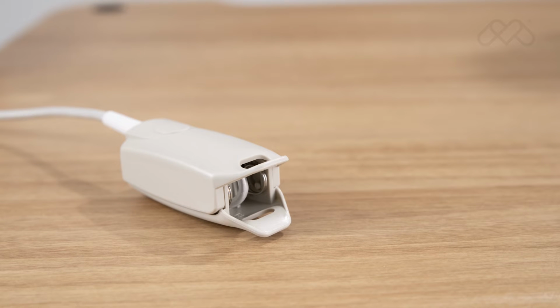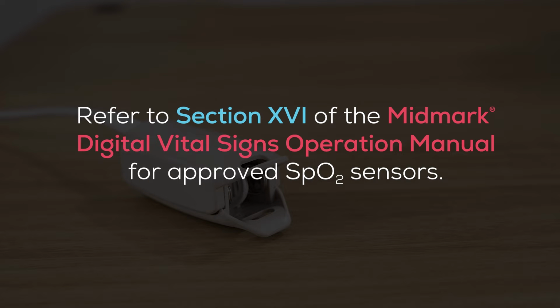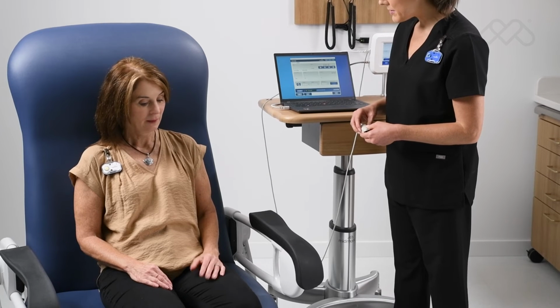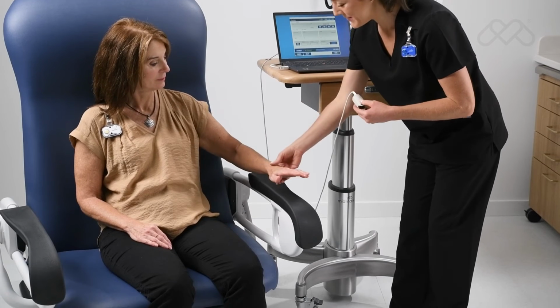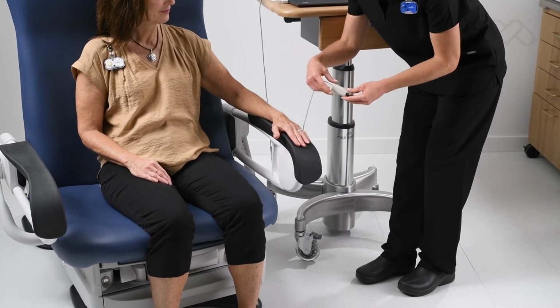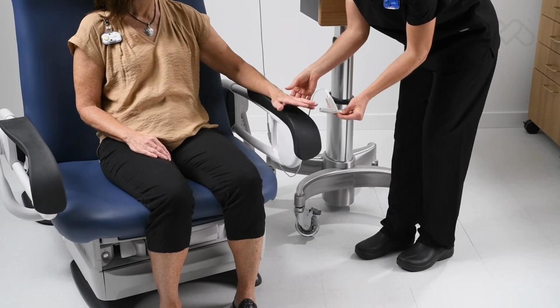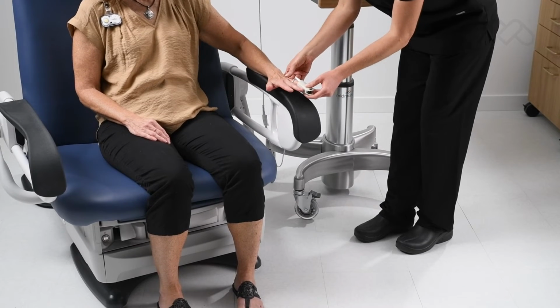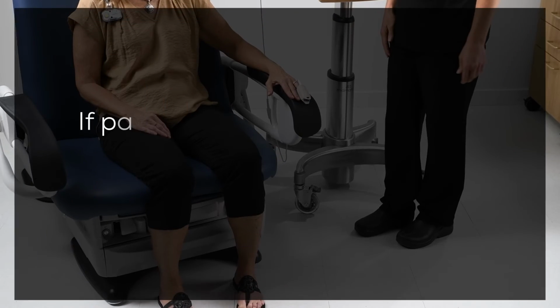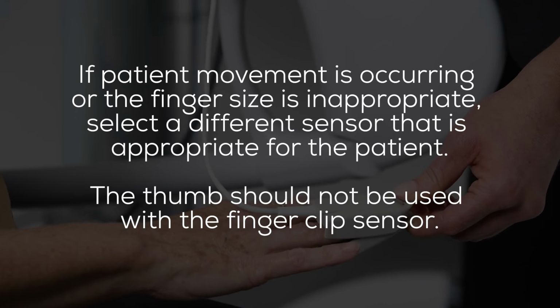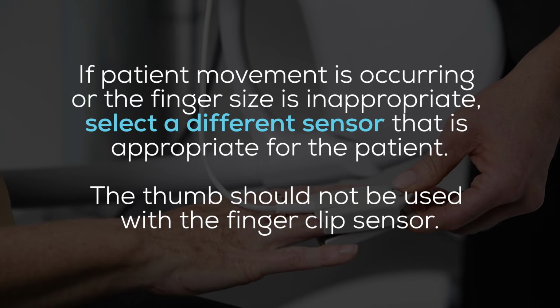clip sensor. Carefully read the sensor directions before using. To perform the SpO2 measurement, insert the patient's finger completely into the sensor. Place the sensor with the LED light position on the fingernail. If patient movement is occurring or the finger size is inappropriate, select a different sensor that is appropriate for the patient. The thumb should not be used with the finger clip sensor.